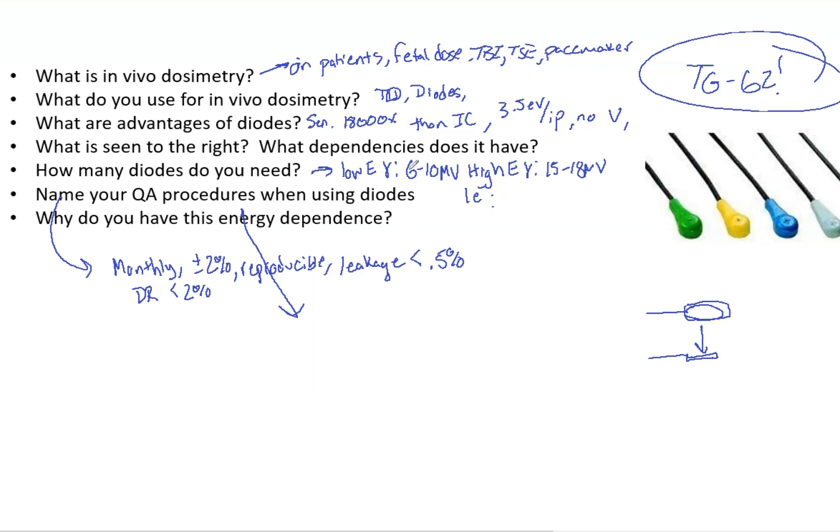So that's diodes in general. And so another thing, they also have SSD dependence, because the dose rate changes with SSD, right? If it's farther away, it is going to have a lower dose rate. And that affects recombination dose rate. There's also a temperature dependence, which is about 0.5% per Celsius degree.